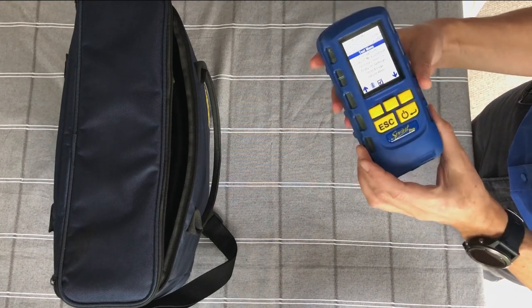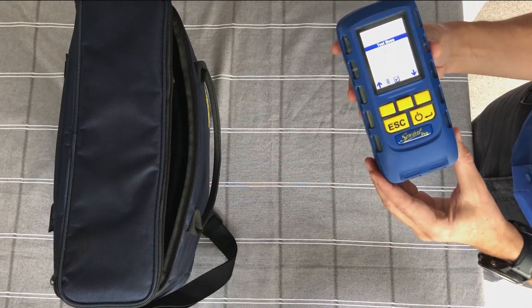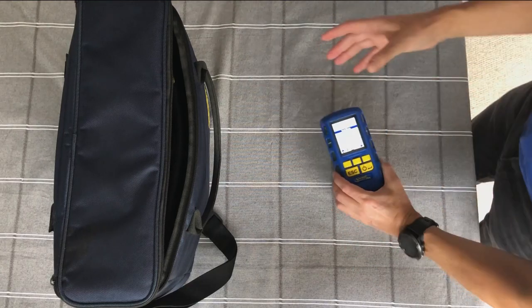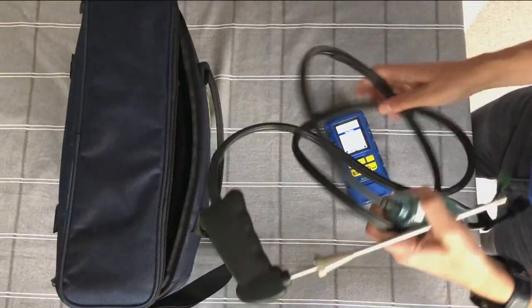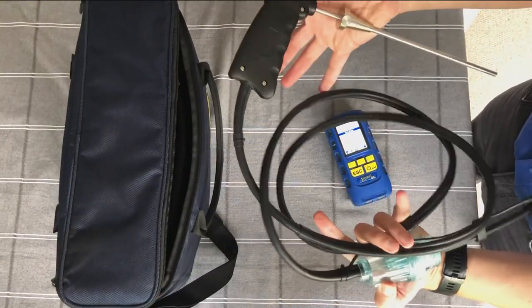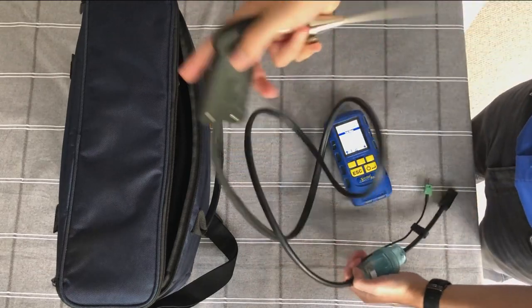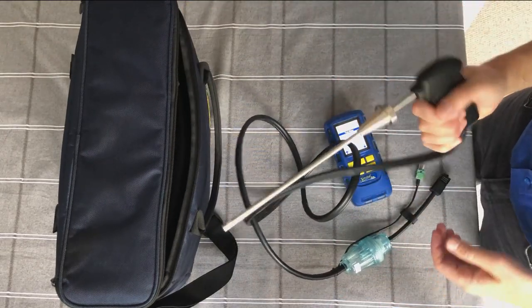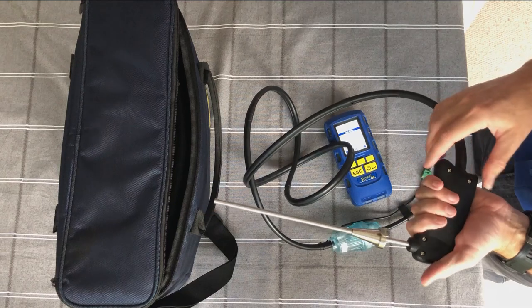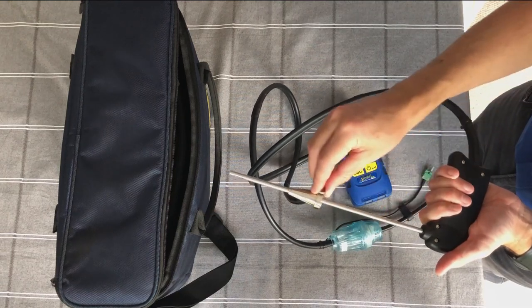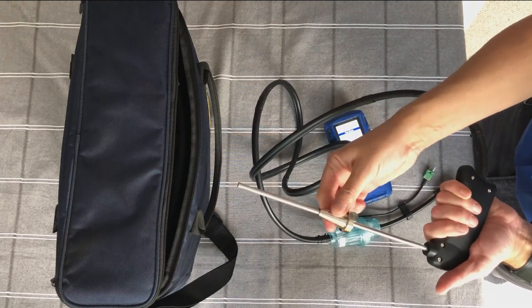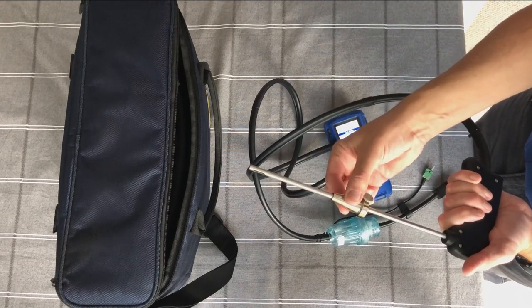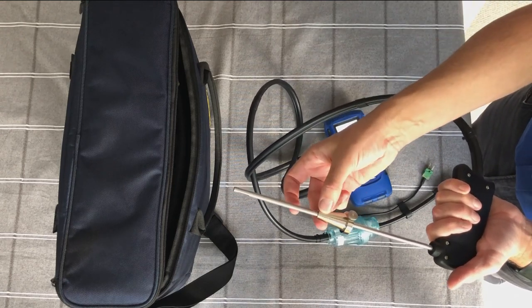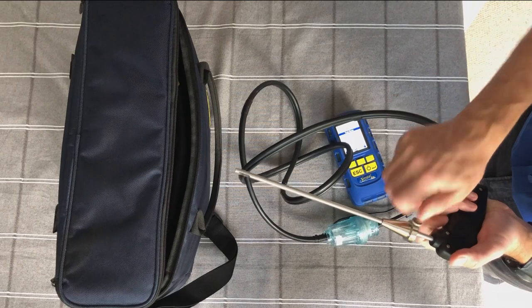Next thing then, I'm going to show you how to attach the flue probe before we get into anything else. So if I pop that down for a second. In the bag, I've got a slot here for my flue probe. This is what the flue probe looks like. Obviously, you've got the end you stick in the boiler itself, in the inspection cap or whatever, and we've got an adjustable depth gauge cone on there that will seal on the different size inspection caps that you might be putting it into.